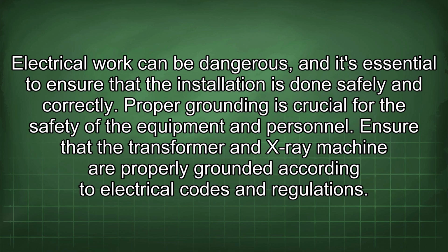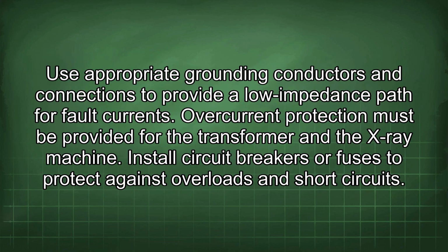Proper grounding is crucial for the safety of the equipment and personnel. Ensure that the transformer and X-ray machine are properly grounded according to electrical codes and regulations. Use appropriate grounding conductors and connections to provide a low impedance path for fault currents.